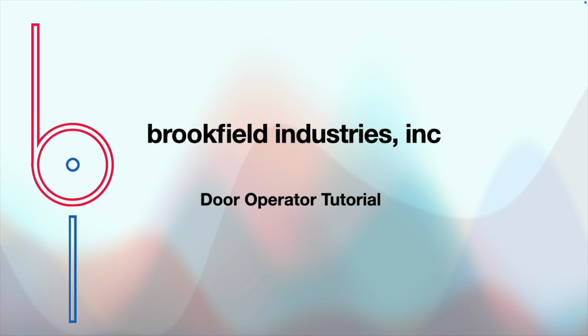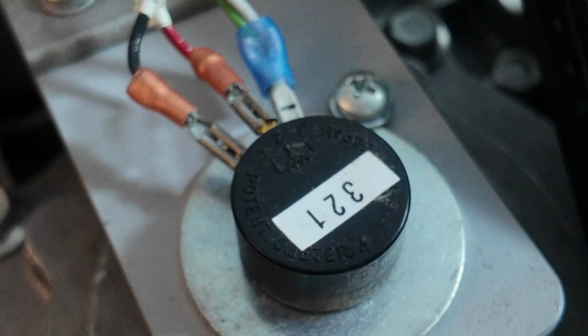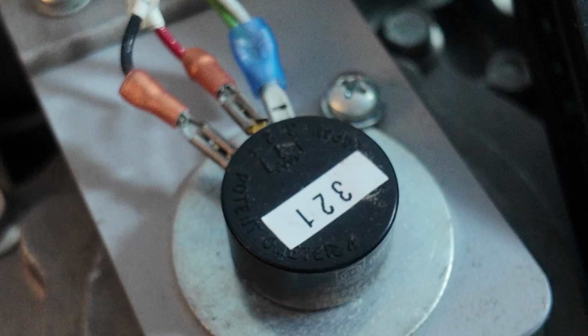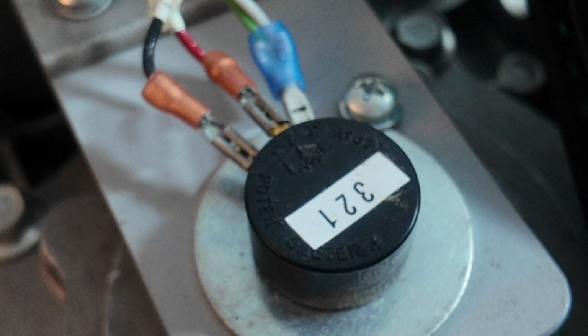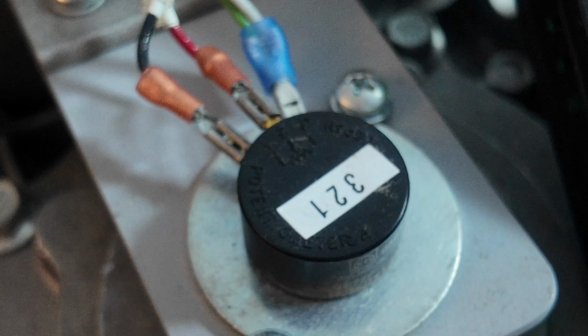In this video, we are going to cover the transducer device that we use for reading the door position of our operator products. The transducer is not an encoder. It is a potentiometer that reads voltage, which is then converted into the digital value that we use for door position. This prevents the need for homing, as it is simply set to the desired position.